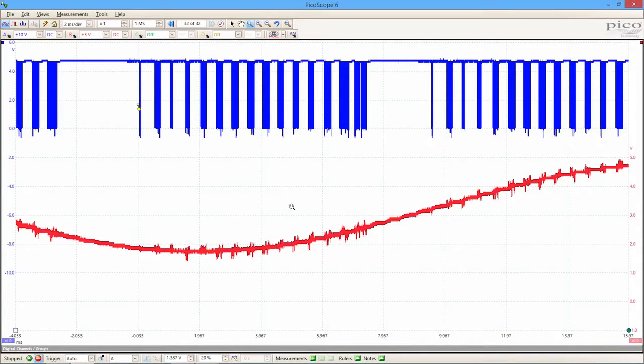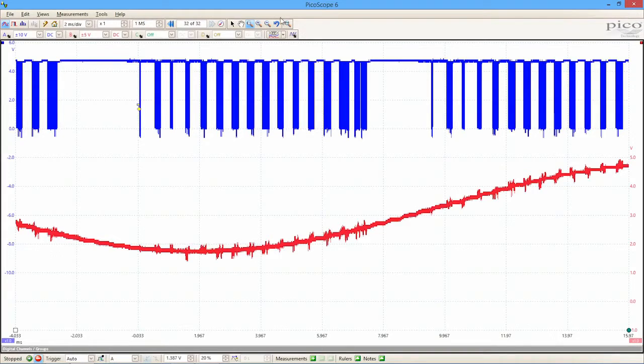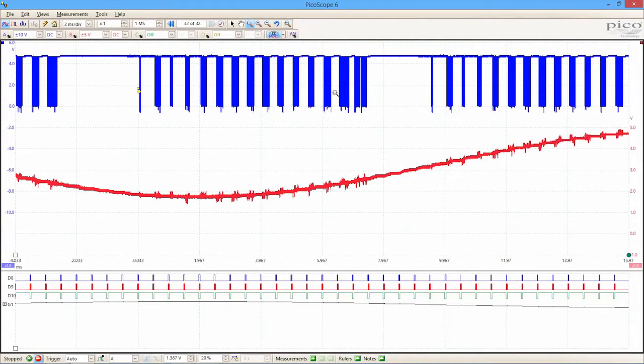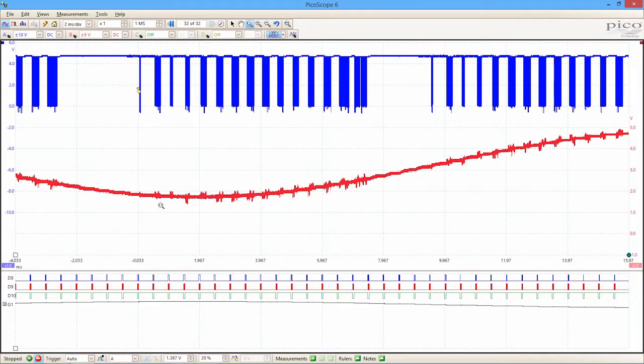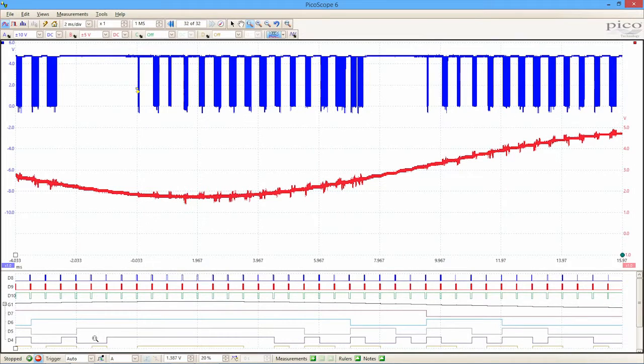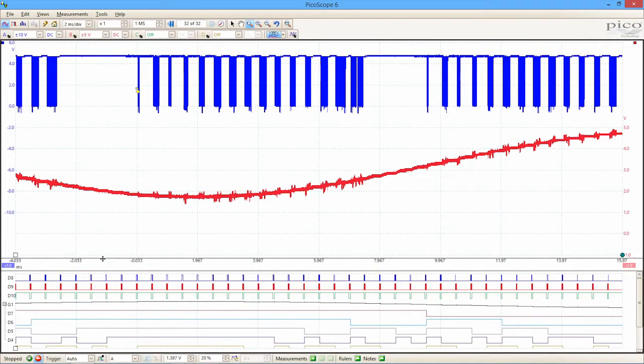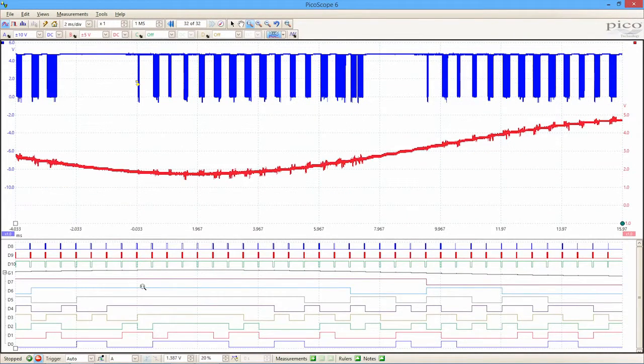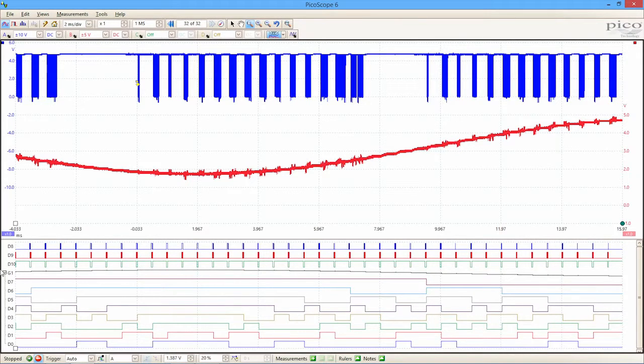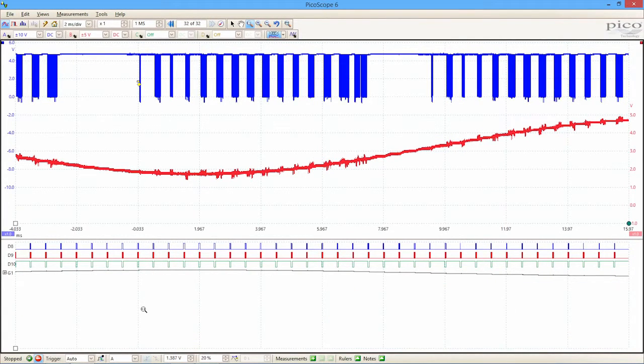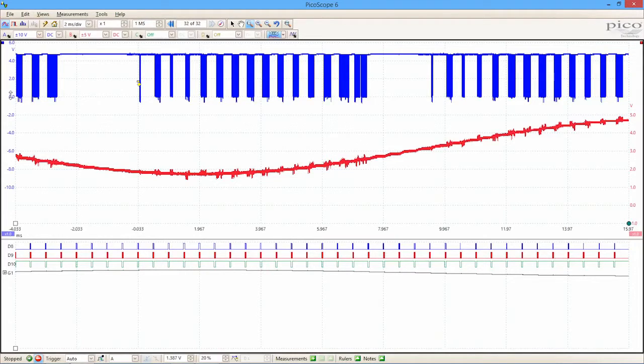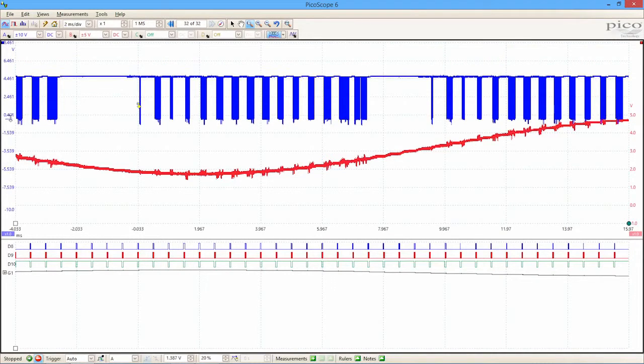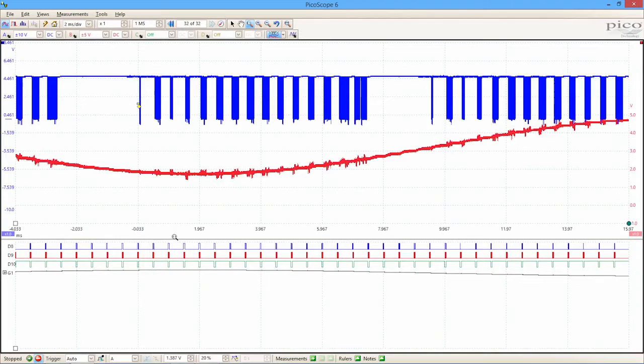What we have additionally in this mixed signal model is the MSO controls just here. So if I press the MSO button there, I get additional information at the bottom of the screen here, and I can just reposition that.